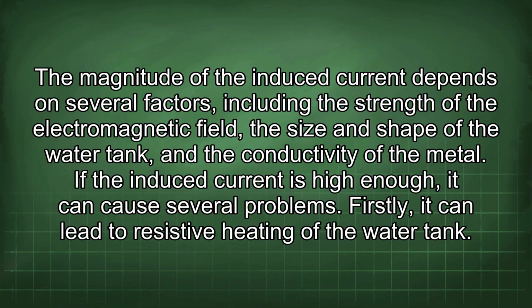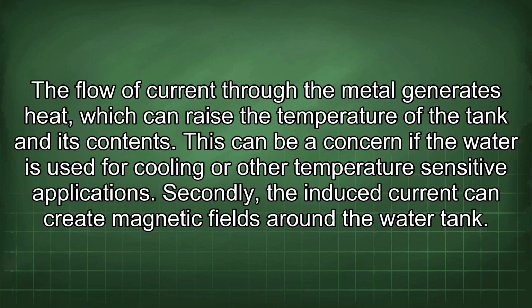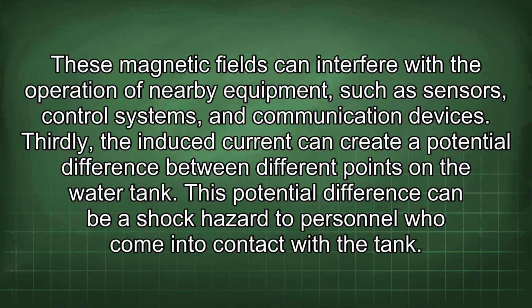If the induced current is high enough, it can cause several problems. Firstly, it can lead to resistive heating of the water tank. The flow of current through the metal generates heat, which can raise the temperature of the tank and its contents. This can be a concern if the water is used for cooling or other temperature-sensitive applications. Secondly, the induced current can create magnetic fields around the water tank. These magnetic fields can interfere with the operation of nearby equipment such as sensors, control systems, and communication devices.